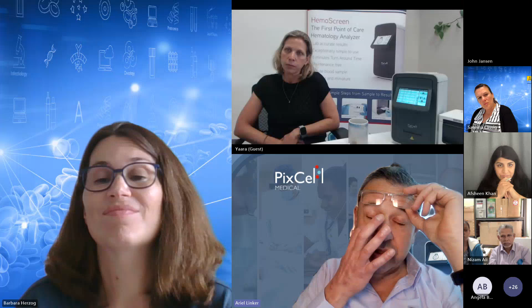Yes, so our AI algorithms can detect the size of a platelet, which is usually around 2 microns. So no problems for the HemoScreen to identify this size of cells. Particles smaller than 1 micron will be more challenging, but there is actually no need, because platelets are usually 2 microns and up. And we have no background noise if we test a cell line or put no cells in the cartridge. So the readings will be 0. The results will be 0 also for platelets. So it's very sensitive and can identify platelets in different sizes.